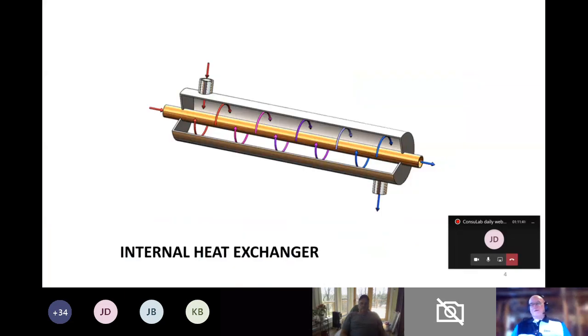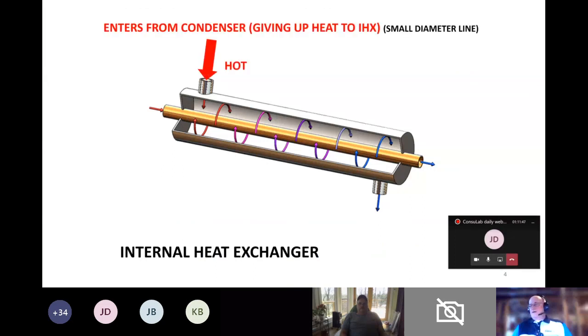This is a graphic that we've designed to help you understand how an IHX works. So we have one smaller high side line that comes from the outlet of the condenser where warm liquid refrigerant enters one end of the IHX. The warmer refrigerant flows through the IHX, giving up some of its heat to the IHX and exits, then flowing to the H block metering device.